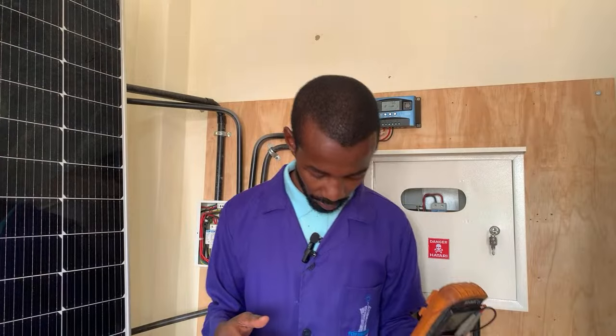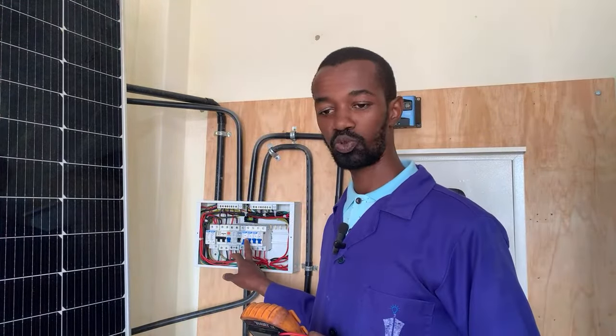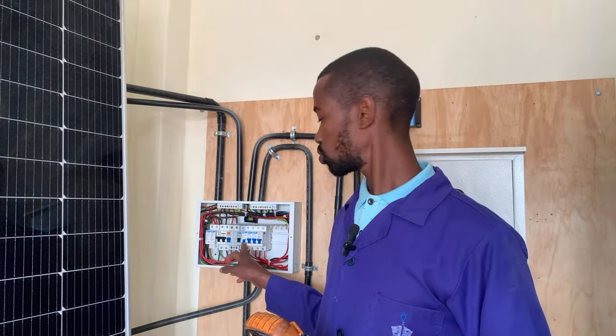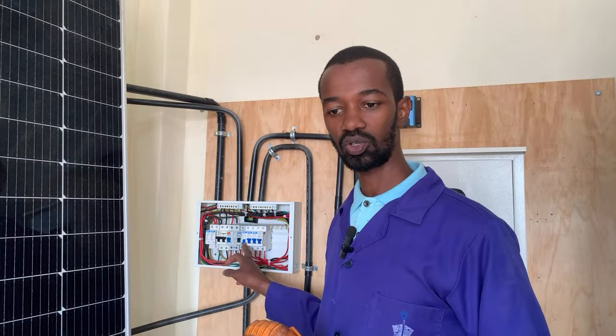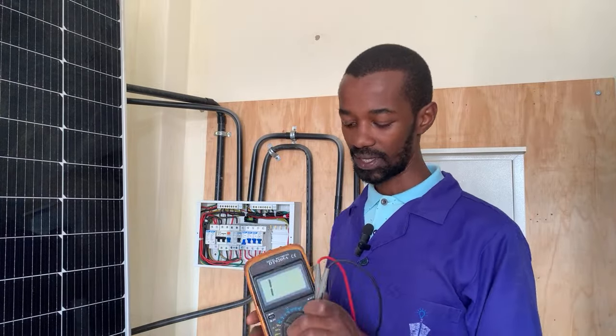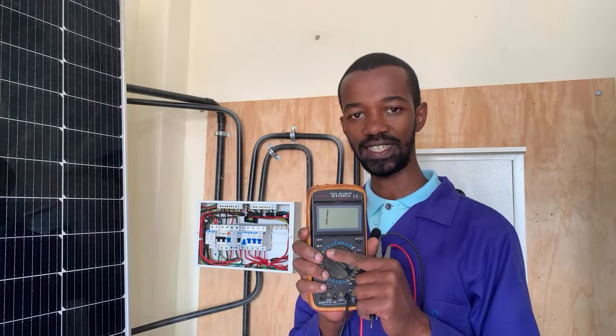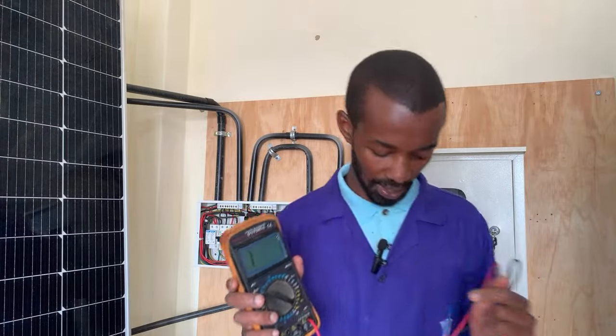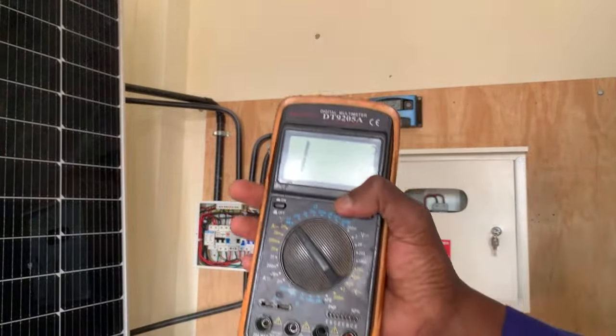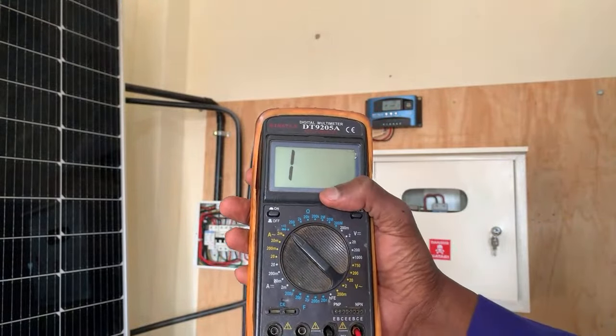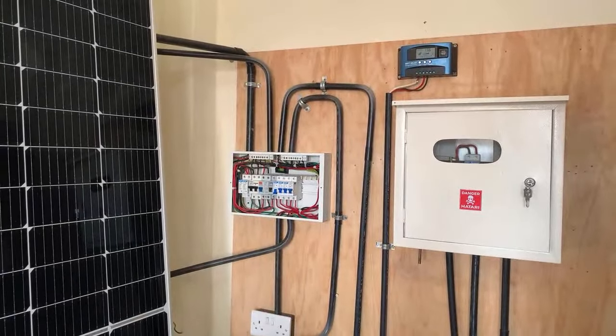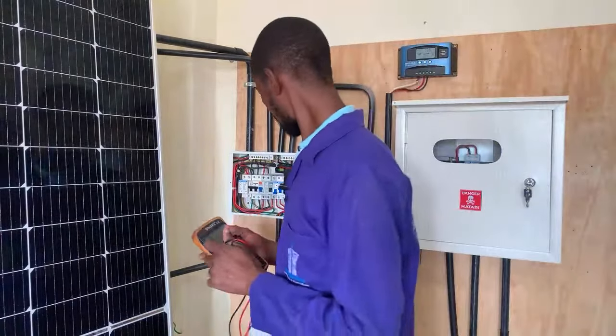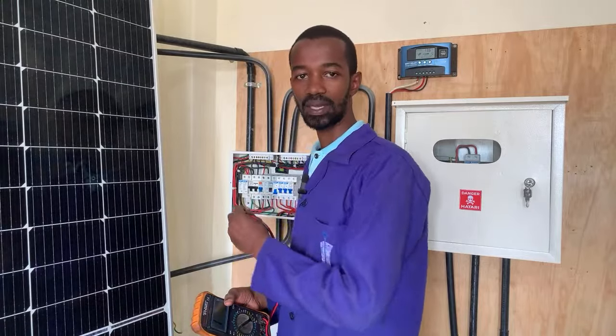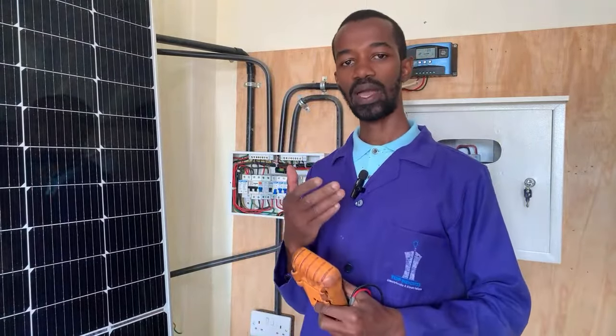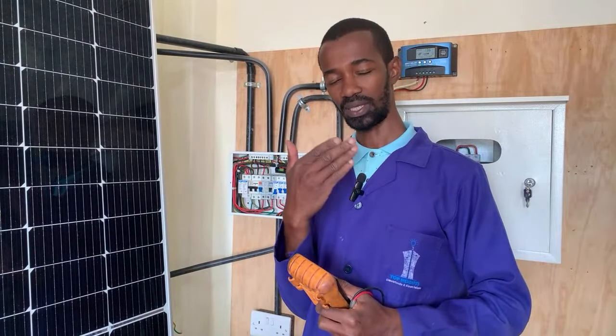Once you have identified where the problem is, before you switch on that specific circuit breaker, you also do the troubleshooting at the consumer unit. This, as we have seen, is done by taking what we refer to as a continuity test, using this multimeter here. You place it at the diode indication, and using your probes, you place them at the output of the MCB, where the cable is going out to feed that particular circuit.